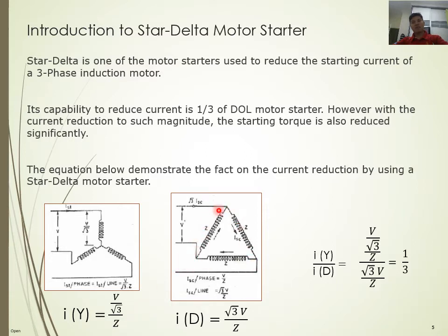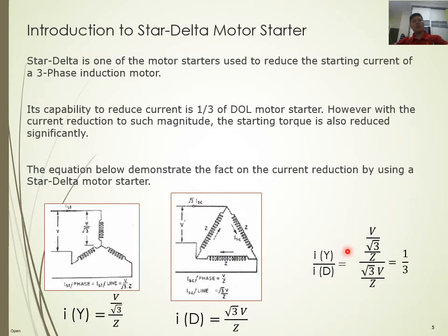For a three-phase delta circuit, the line-to-line voltage and the phase voltage are equal. But the line current is greater than the phase current by root 3. By knowing the equations for star and delta current elements and doing the mathematical derivation, we get a value of one-third. This tells us that starting the motor in star and running it in delta gives one-third of the current compared to starting directly in delta.